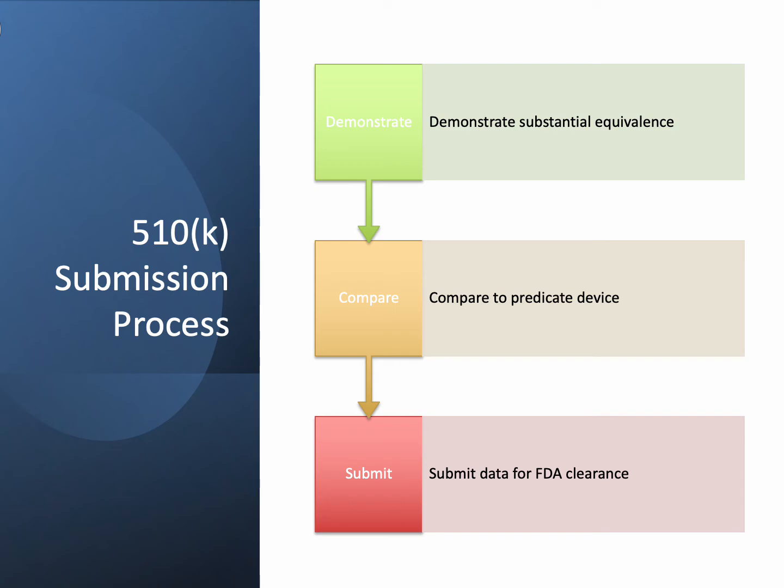The FDA reviews submissions within 90 days, issuing a substantial equivalence (SE) determination for market clearance. Ethical considerations include truthful data, avoiding exaggerated claims, and ensuring patient safety. This process aligns with course objectives by enabling compliant market access for moderate-risk devices.